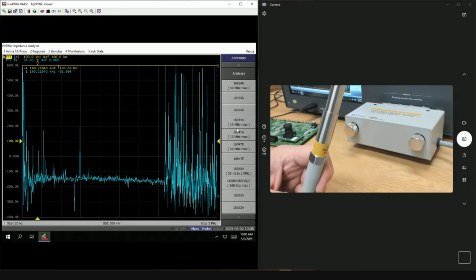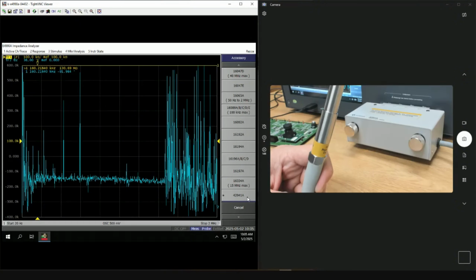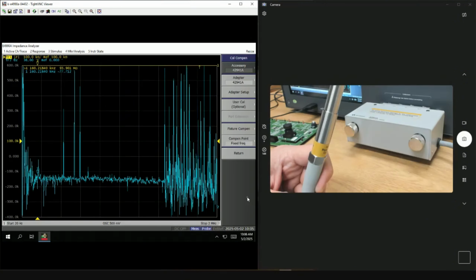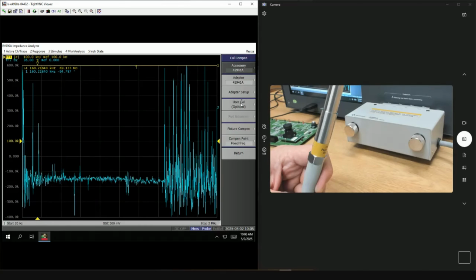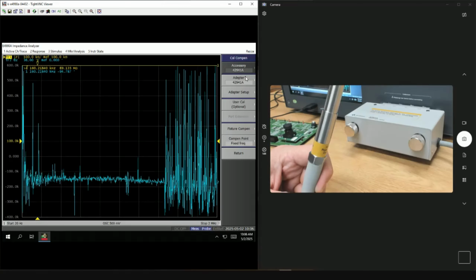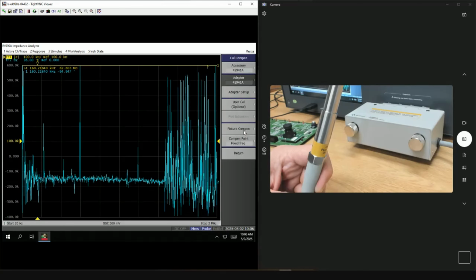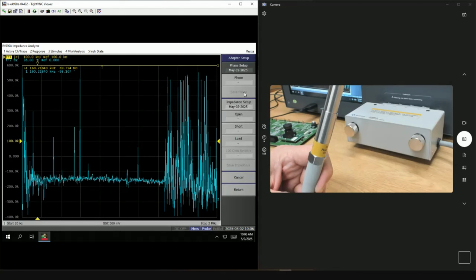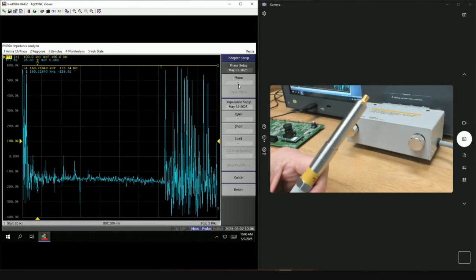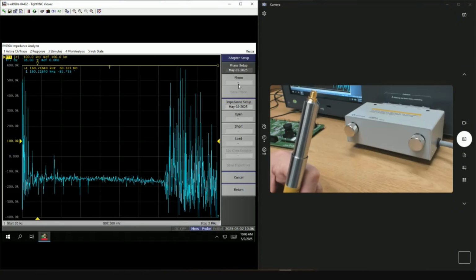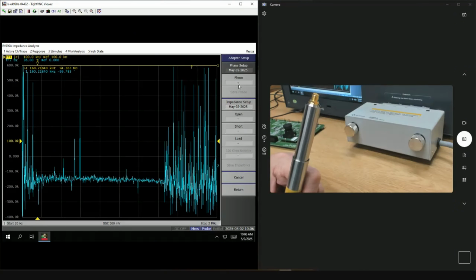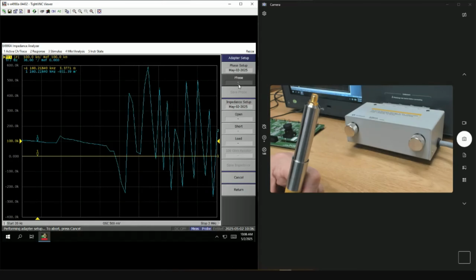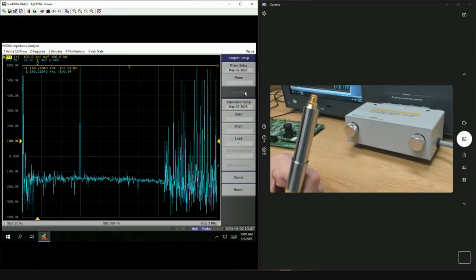By default, it's not selected as this 42941A, so this is why I'm going to select it, because these are the accessories that are connected to it. Then I'm going to do this. The first thing is adapter. So this is a probe, and then adapter setup. According to the service guide, the user guide, first you leave the probe head open as it is, and then you do the phase. It'll take a while, and once it's done, it will show up over here. It will take a couple of measurements before it's finished. So it's done. So we'll save this.